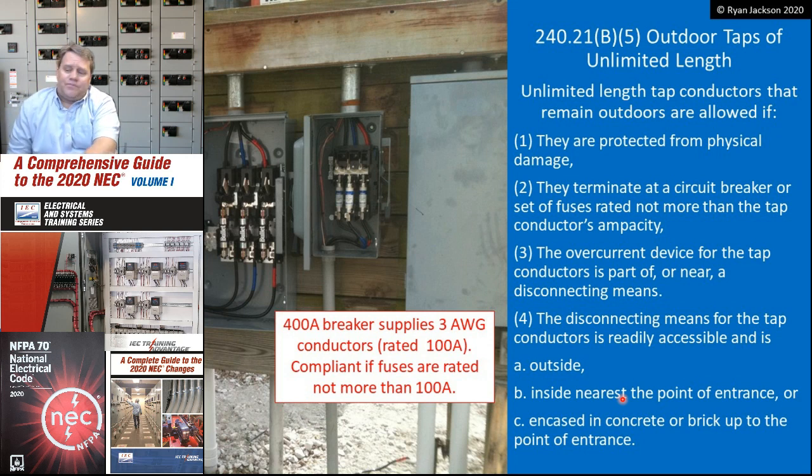With that said, that's pretty much all there is for feeder taps. They're really not that bad. Again, once you understand the concept, ground fault and short circuit protection upstream, overload protection downstream. It's just like a motor or it's just like an air conditioner. It's treated the exact same thing, the exact same way.